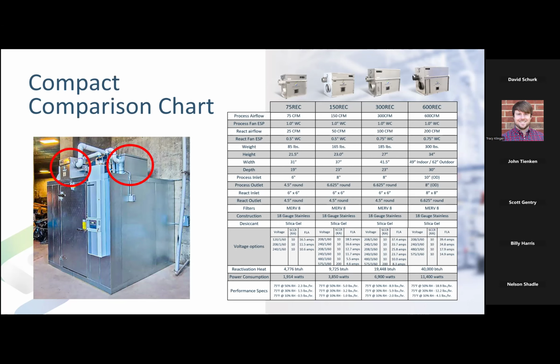And everything ices up over a period of time, including the evaporator inside this unit that's having to condense that moisture that comes in. You know, it's putting out minus 10 degree air to maintain a 0 degree Fahrenheit environment. So it's going to frost and freeze almost immediately. And in fact, many times you'll have two evaporators in there. And when one frosts or freezes up, you turn it off and defrost it and turn the other one on. Well, what we do with desiccant dehumidification is to provide very dry air to these environments at a low enough dew point temperature that it will actually sublimate the moisture out of the ice into the air. It will pull the moisture out of the ice without having to condense it, sublimate, and help keep these environments dry. Really cool stuff. It's amazing what you can do with these.